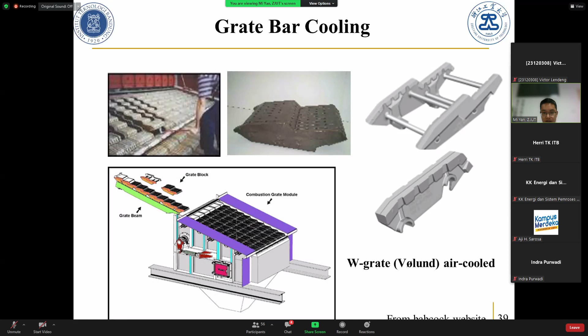And this piece is the air cool, and this is the water cool. The grate surface cooling is independent, so that the air can be added and adjusted for optimum combustion. Actually, some companies can design it so you can change: when the LHV of the waste is lower, they use air cool, and when your MSW heat value increases, you can change your grate piece to water cool.